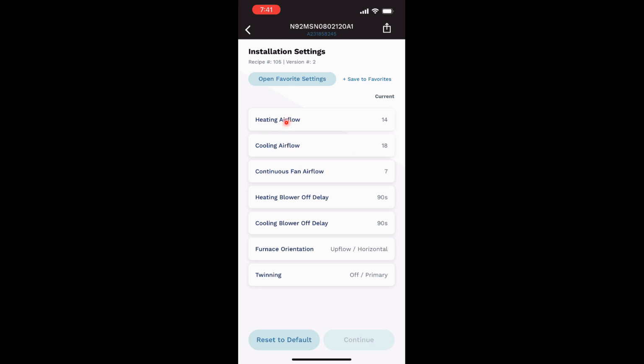This lets you go in and set all this by what you set your ductwork at and what your guesstimated static pressure should be. So you should know if you're at 0.10 or 0.08 friction rate that you're going to be able to get into that 0.50 range, especially if you upgrade your return grill just a size bigger. You shouldn't have any problem getting to the 0.50 range. So you could go in and actually size this up and say, okay, I need my heating airflow at 14, cooling at 18, and my continuous fan is going to be here, and I'm going to do a 90-second delay on both of those.